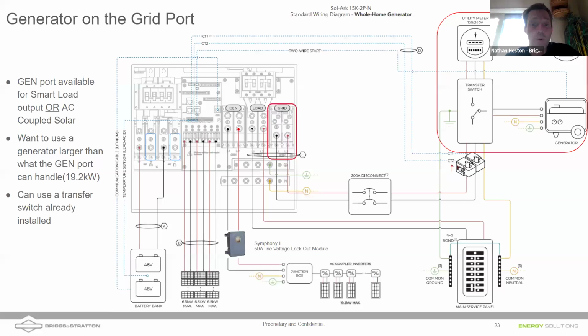Well, Briggs has got a cheaper and better solution, right? In the unlikely event that both are running at the same time, say an evening where the grid is down and your solar is there but just not enough to keep up with the loads of the home, we can use one of these lockout modules. They're relatively inexpensive, something like $120, right? You can then prevent ever having that generator and the AC coupled solar on the AC bus at the same time. It's a really nice option that's fairly unique to Briggs and Stratton, having the ability to integrate with our transfer switch a smart lockout module, a line voltage module, that just takes the AC coupled solar off when that generator is on to charge the batteries.